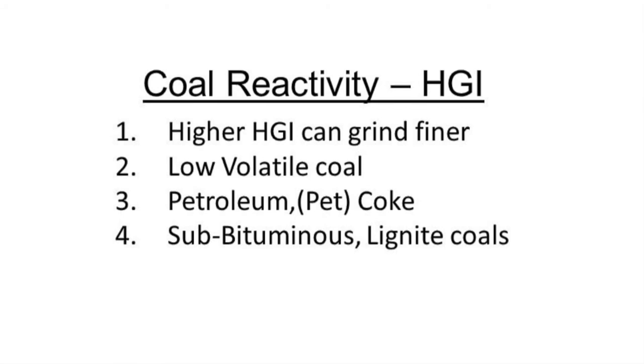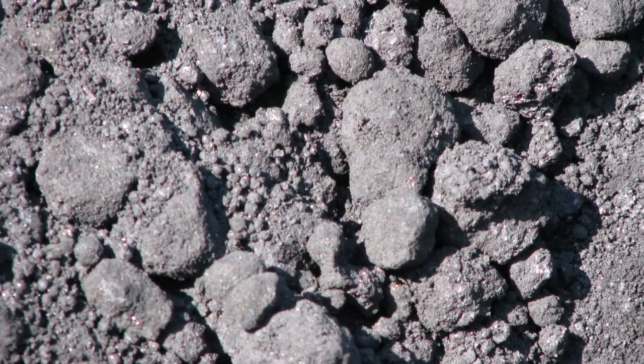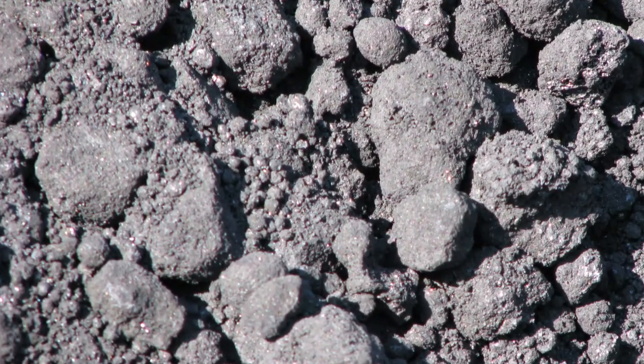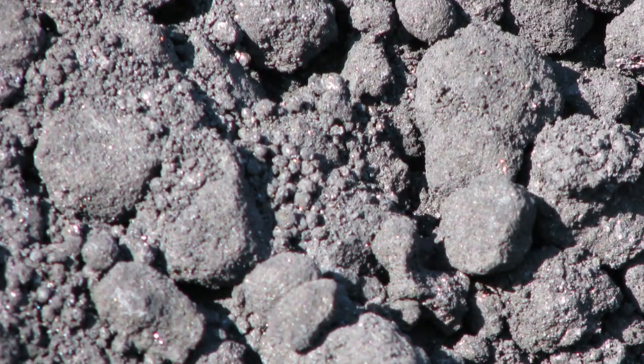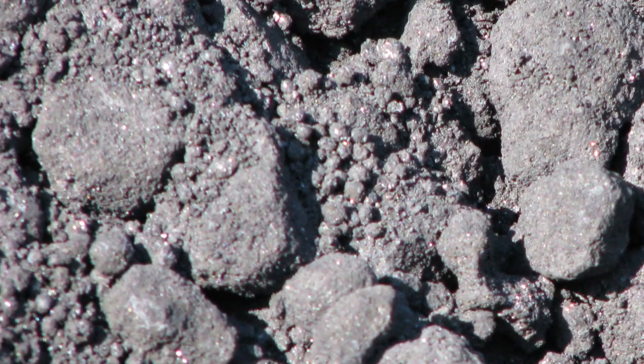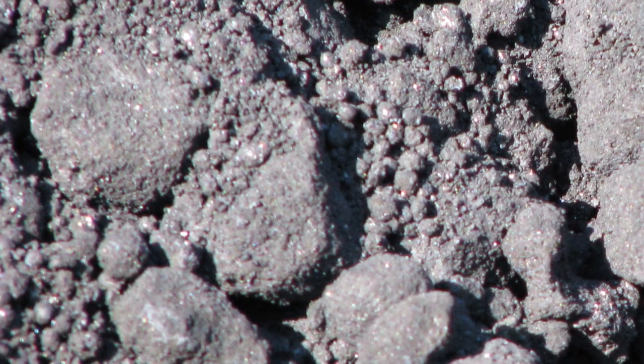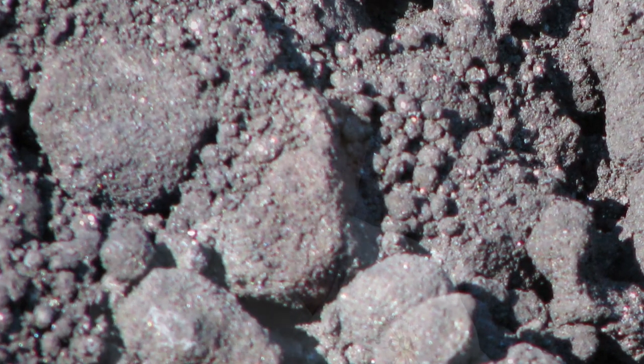Petroleum cokes are always low volatile, and there are two basic types. A sponge coke is a little more crunchy, can grind up, and might have a Hard Grove Grindability in the 40s or 50s. Then there's shot coke, which consists of little or big round balls and may grind only in the 30s. So even though sponge and shot coke may have similar volatile matter characteristics, it's harder to use shot coke because the HGI is tougher — making it harder to grind to the small particles that a low volatile material would need.